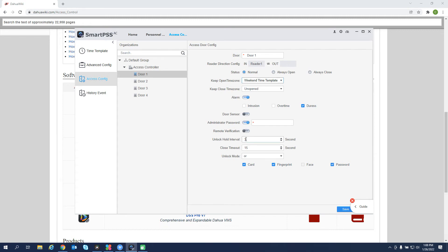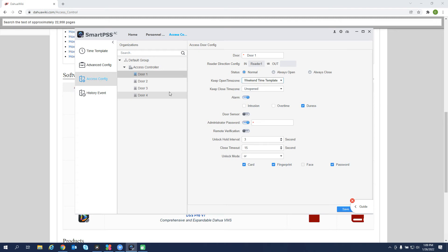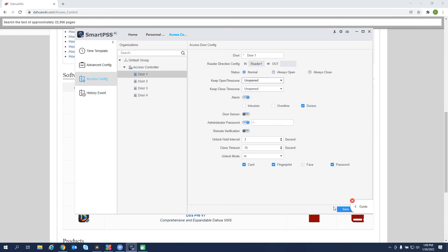And unlock hold interval. So when there is a swipe, how long do we want that door to stay open or release? It is three seconds by default. You can raise that here if you need. And then the unlock modes that are available for the readers. You can get a per door selection here. So we're going to hit save. Actually change that. Save.